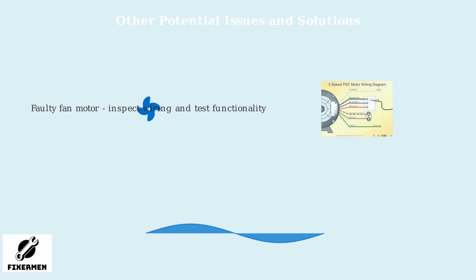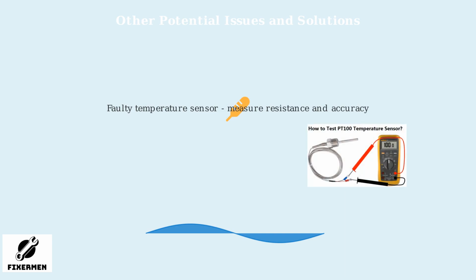If the L2 error code persists even after cleaning the condenser coils and verifying refrigerant levels, there may be other underlying issues at play. One common culprit is a faulty fan motor in the outdoor unit. This can cause inadequate airflow, leading to heat buildup. A malfunctioning temperature sensor can also trigger the L2 protection. These sensors monitor the unit's temperature and may need resistance testing.